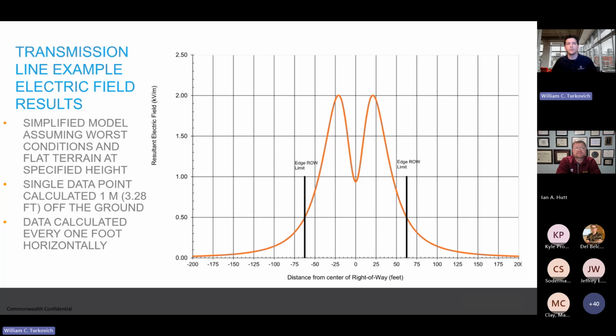One other thing about being conservative is one of the baked-in assumptions that we use: there's a certain voltage difference that transmission lines can operate at on a daily basis, continuously, without being tripped off by protection. This specific example was run at 105% voltage, because in that specific utility, you can see it will continuously run at 105 to 95% voltage. The electric fields are directly related to the voltage, so that's just another example of how we can bake conservativeness into these projects to add that protective value.